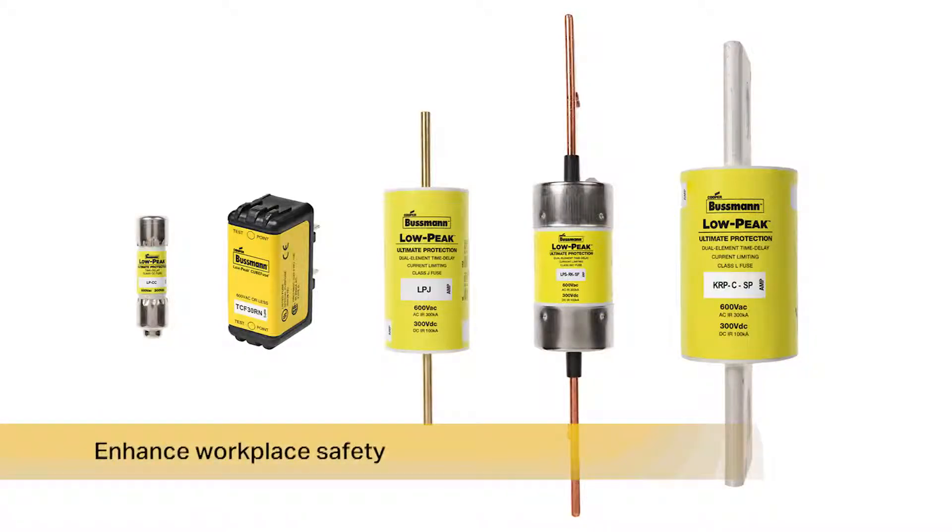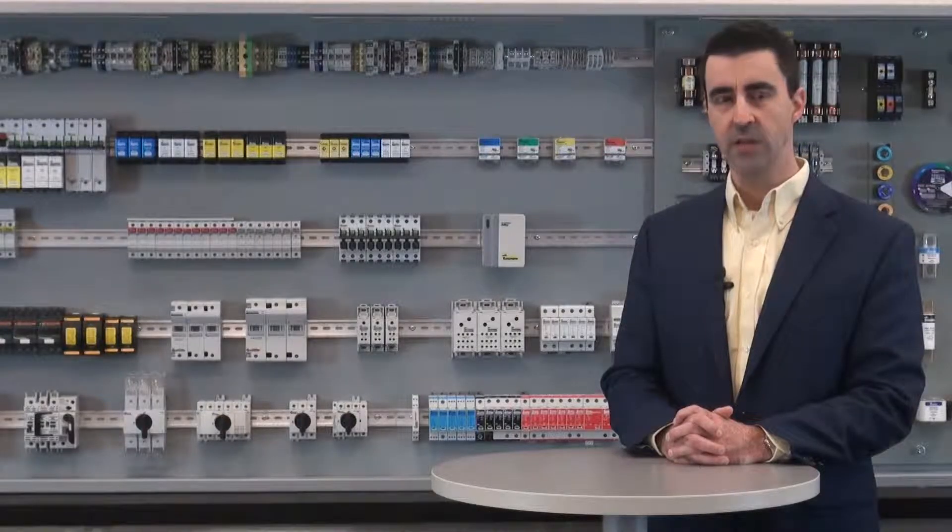Fuses that limit the let-through current to downstream components provide protection from thermal and magnetic forces while providing numerous benefits. Current limiting fuses enhance workplace safety by reducing the incident energy personnel are exposed to under fault conditions. Arc flash hazards may be greatly reduced when compared to using a non-current limiting overcurrent protective device, especially at 600 amps and below.